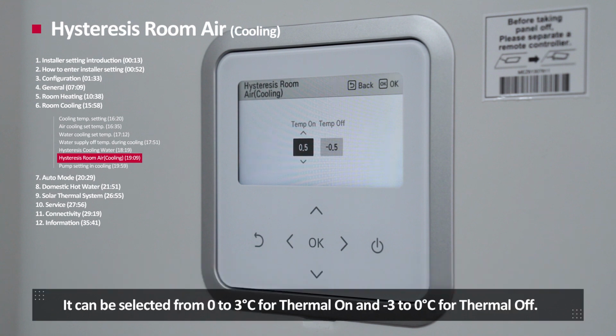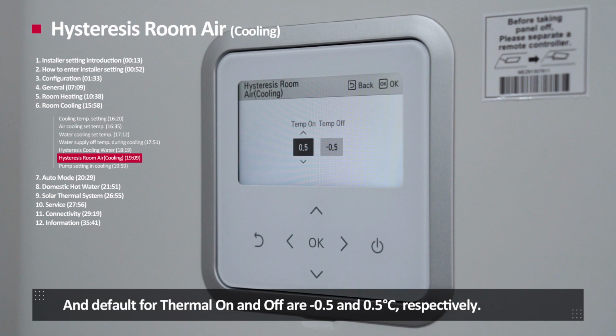It can be selected from 0 to 3 degrees Celsius for thermal on and negative 3 to 0 degrees Celsius for thermal off. And default for thermal on and off are negative 0.5 and 0.5 degrees Celsius respectively.